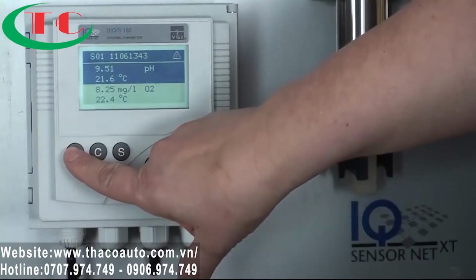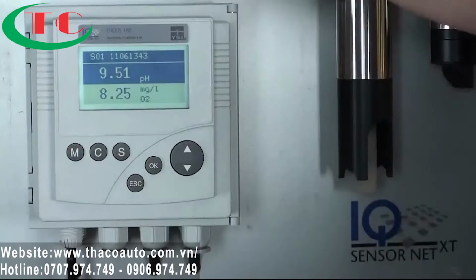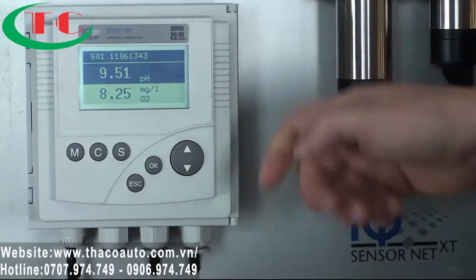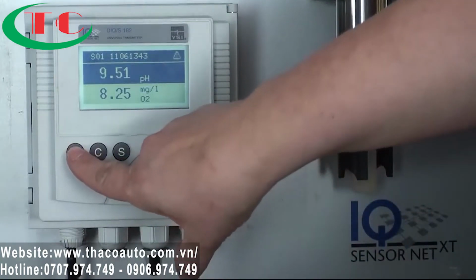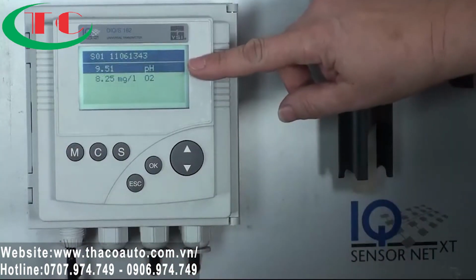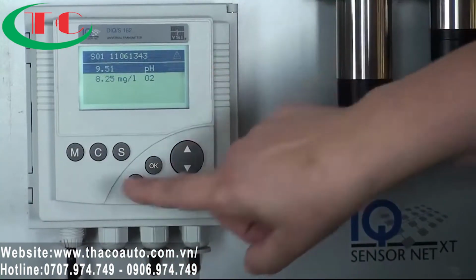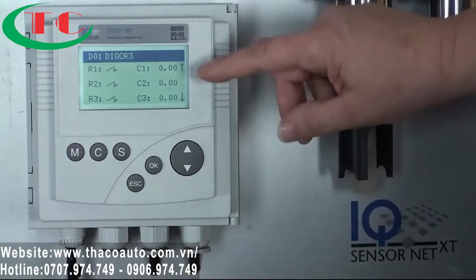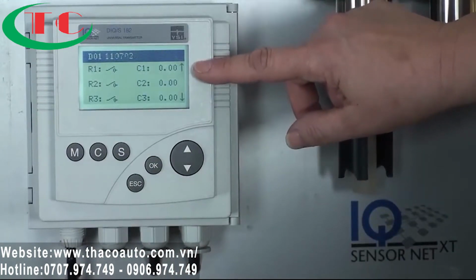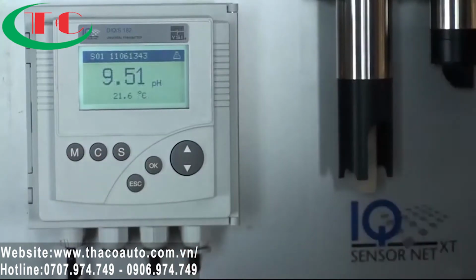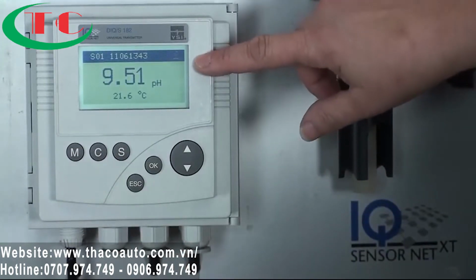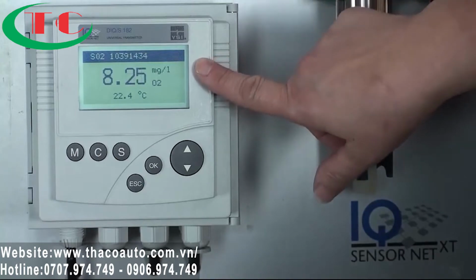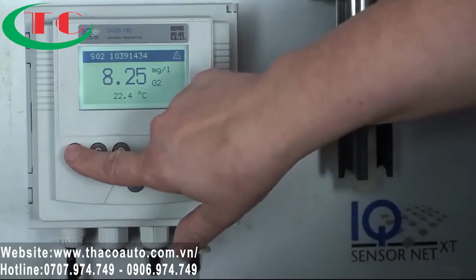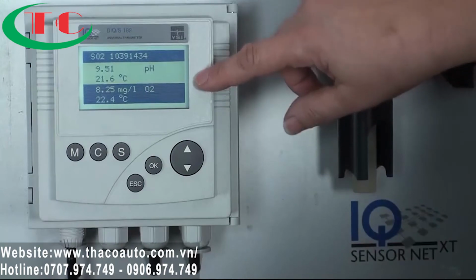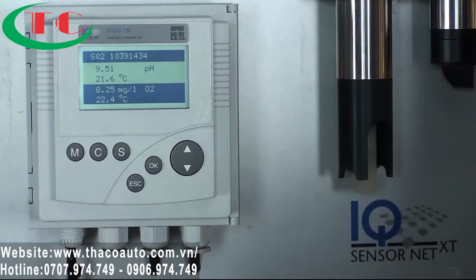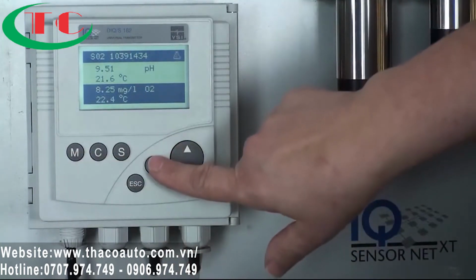The M button will help you scroll through the menus. As you can see, I can press the M button again. It's going to show me my 2 sensors in smaller font. Press it again, it's going to show me the outputs and links in my relays. I press it again and I see 1 sensor. It'll scroll to my second sensor because I have 2 sensors installed here. And I can press it again and then I will be back on that original screen where we can see both of the sensors. From here I'd like to cover the OK button.